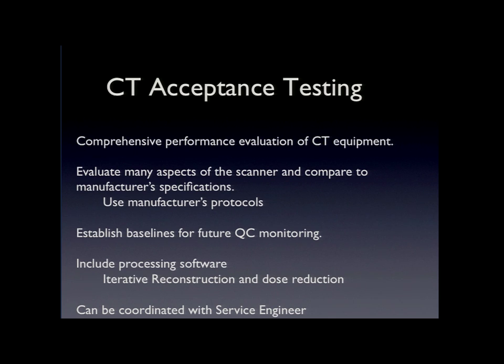First of all, when you first get a new CT scanner to your facility, the ideal situation is to perform acceptance testing on it. That's a very comprehensive performance evaluation of the CT. You evaluate many aspects of the scanner, and you compare it to the manufacturer's specifications. You told me if I give you this much money, this is what this is going to do, so you want to make sure it's doing that. It's a very comprehensive and time-consuming operation. It's ideal to do that, but it's not always completely done.